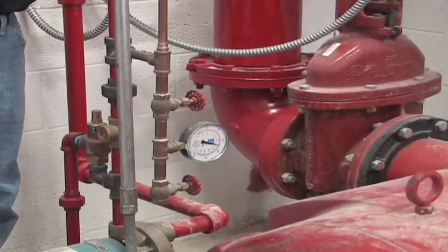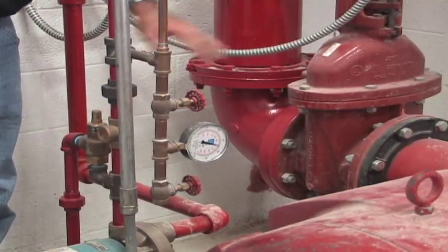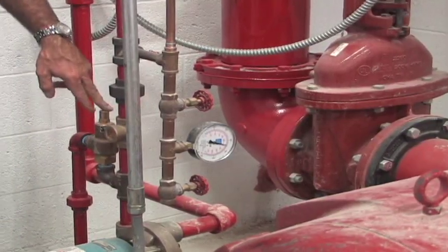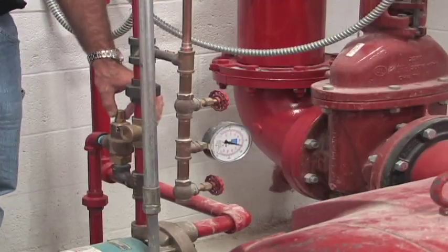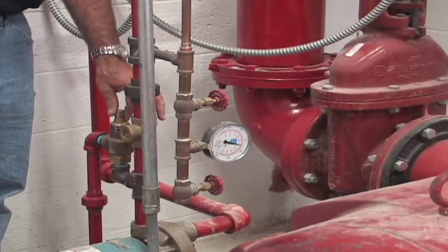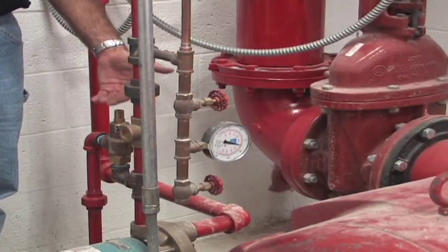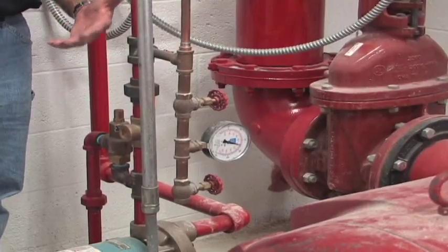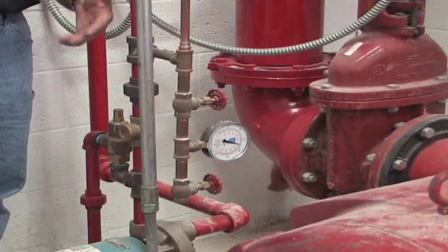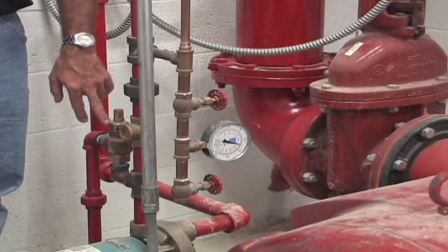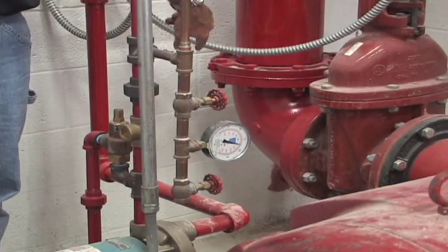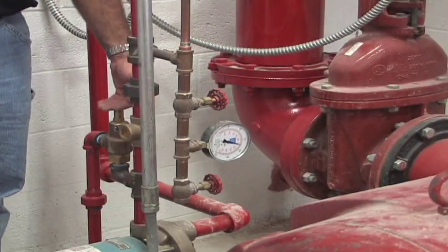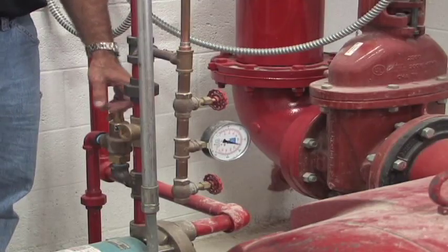On both of our jockey pump and our fire pump, both of them are set up with a pressure relief valve. Both of these are set at 175 to 185 psi. If for any reason the fire pump or the jockey pump should build up any more pressure, it will not go into the system. Both of these are tied back into the drain system, which will drain outside the building. Both the fire pump and the jockey pump have this.